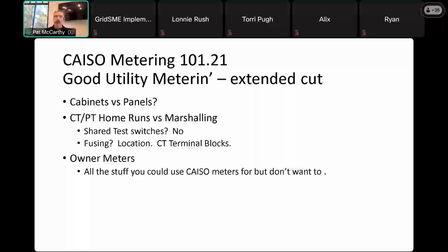As I mentioned, they're often involved in control schemes, but there's a jurisdiction issue to understand: CAISO has jurisdiction over those meters, and that jurisdiction—in terms of time synchronization or password protection—does not marry well with some of those other ancillary applications. If you're doing controls correctly, using a purposeful protocol like synchrophasors, you need 1 millisecond time synchronization at all times to any device producing data on that protocol. You cannot have that kind of time synchronization on a CAISO meter—it's just a conflict of rules.